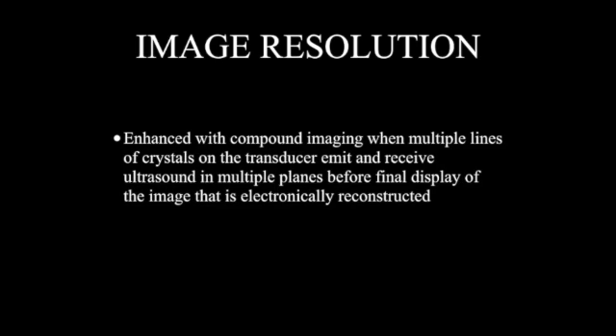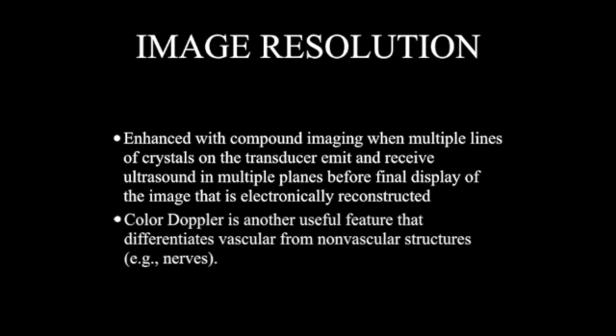Image resolution can be enhanced with compound imaging. Multiple lines of crystals in the transducer emit and receive ultrasound in multiple planes, and the images are electronically reconstructed before display. Color Doppler is another technique that is useful to help differentiate vascular tissue from other tissues that you are scanning.